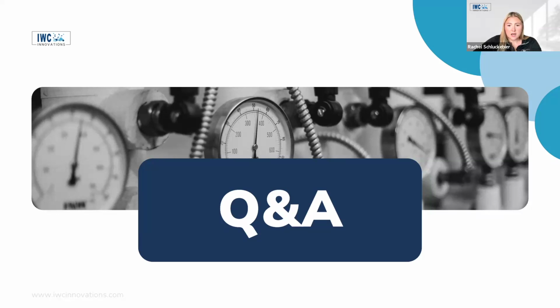Let's see, we got a couple questions on filters. Do you recommend point of use filters for regular use as a prevention method? It depends on the facility and the building. Of course, a filter in place will ensure that the user of that outlet has no exposure to waterborne pathogens, including Legionella. But they also do reduce flow. So you need to be careful that if you have filters in place, you're still implementing a flushing program that's keeping water moving through the pipes in the way that they were designed. You don't want to accidentally increase stagnation in other areas of your building by having point of use filters in place.